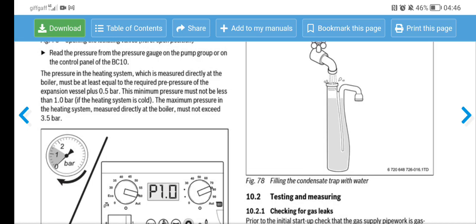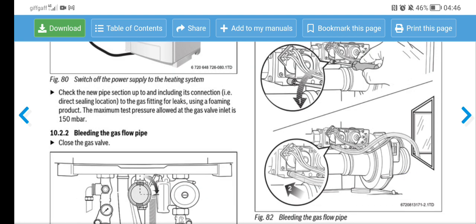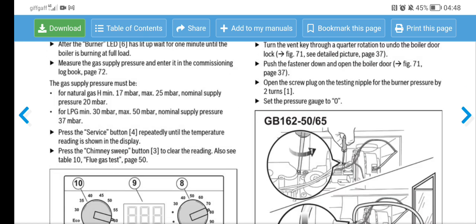Log that reading. Do remember on these to clean the condensate trap out and fill them with water afterwards. Remember to check your working pressure. All five boilers were operational, got 22 millibar working pressure.